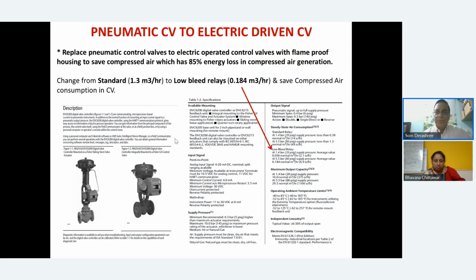MOVs, electrically operated MOVs with the ATEX rating. The second thing was, there are control valves, but the control valves have two kinds of relays. Steady state, standard relay. Normally L1, L2; you take L1, the standard relay. Standard relays at 5.5 bar consume 1.3 meter cube per hour. It is a continuous consumption. It has to bleed whether it's operating or not operating, because it has to sense that yes, there is compressed air. Otherwise, system failure will go to DCS.